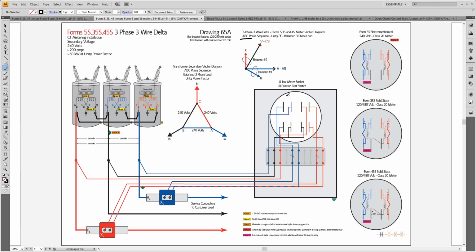And so as we see this, again, if I was going to install one new, and I was going to put a 35S into this installation, I really don't need to jumper these two. I would just have to connect to that terminal, and so I would just bring B phase up and connect to there, and that gets B phase to the non-polarity side of this potential coil, and B phase to the non-polarity side of that potential coil. If I was going to install a new 45S in a 3-phase 3-wire delta, again, I don't need to put anything on this one, just need to put it there, because that will get non-polarity on the blue and black coil and non-polarity on the red and black coil.